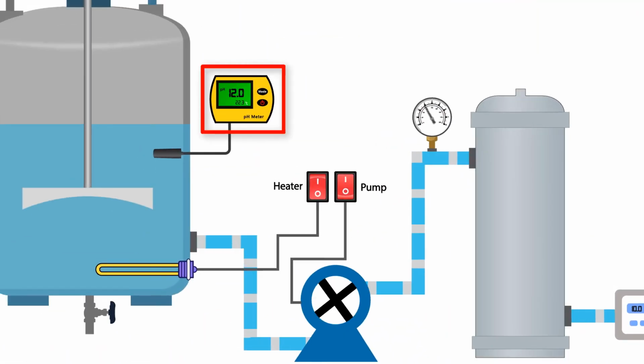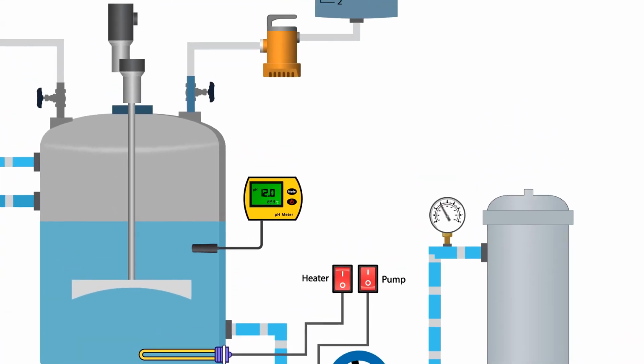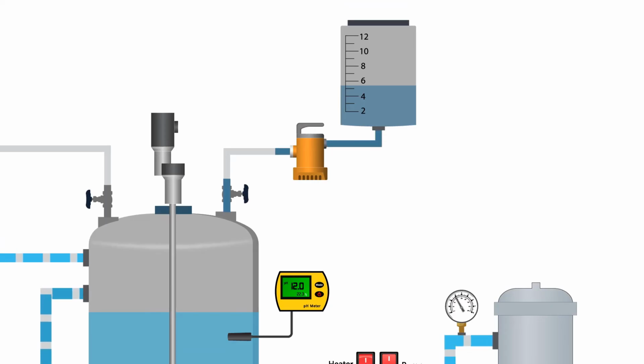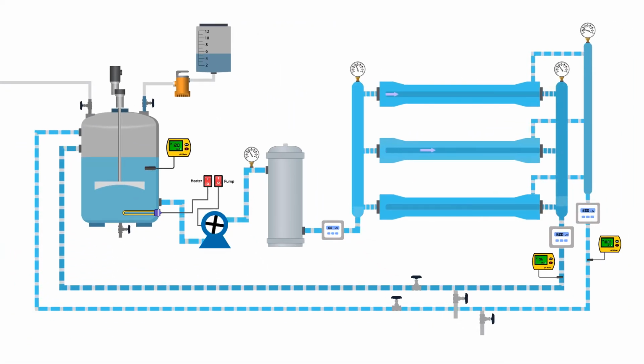When the solution reacts with microbiological and suspended particles, it becomes less concentrated, causing the pH to change. If the pH of the prepared solution decreases, add more sodium hydroxide to the mixer tank to maintain a pH of 12. Continue this process for about 45 minutes.